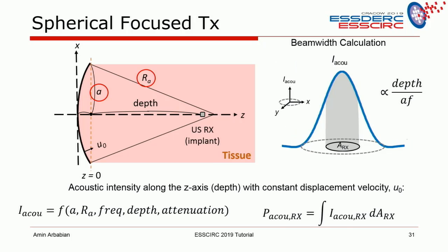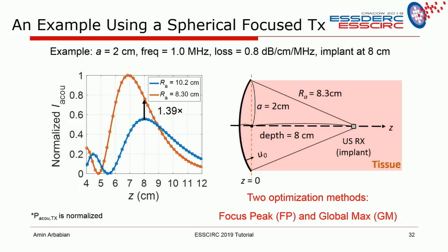Now this effect leads to something interesting. And that is, if you want to focus at a given location, let's say I want to focus to 8 centimeters deep in tissue, right? And I have two options. On that desired location, so that's what we call a focal peak or focus peak. This is the blue graph. So I've designed a transducer array to focus right at 8 centimeters, and I'm getting so much power. So that's option number one.